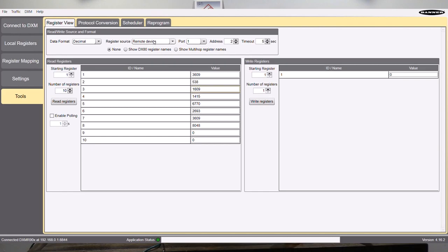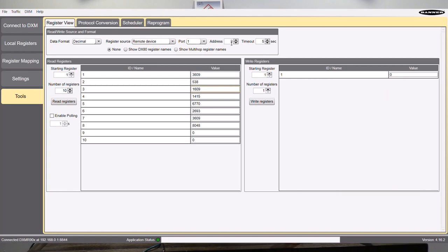I'm connected to port one and this particular sensor has actually been reassigned from the factory default of one to two. And I do recommend changing all of the sensors or devices connected to this to anything but one because that's actually what they come from from the factory. So if you have a bunch of sensors you try and connect, they're all in one, you're going to have some conflicts. So always start at two and above.